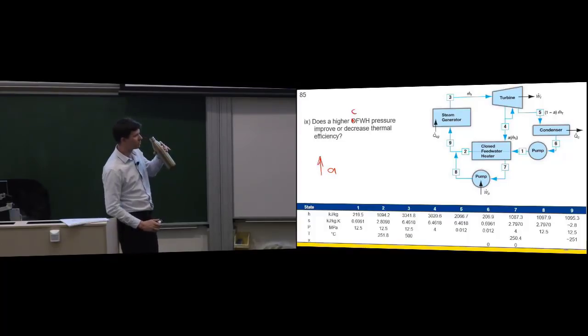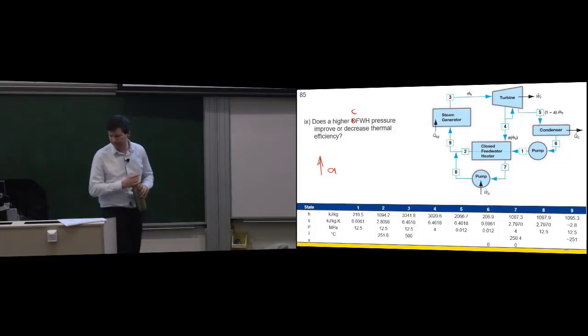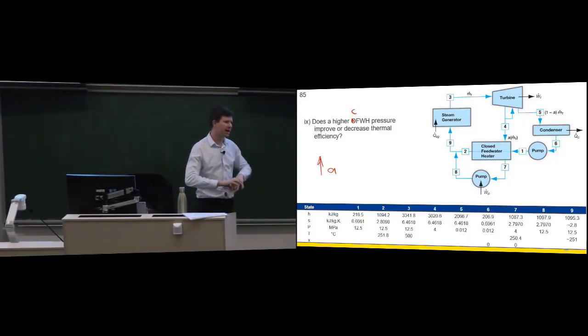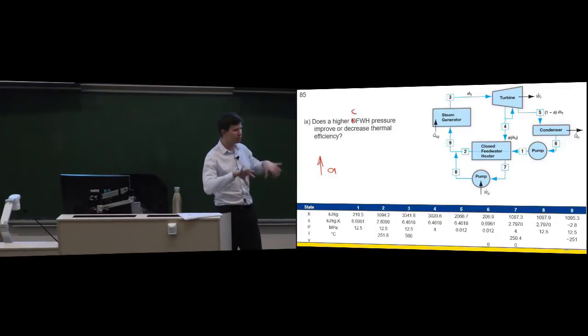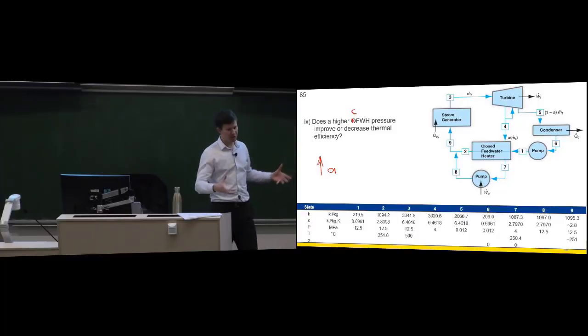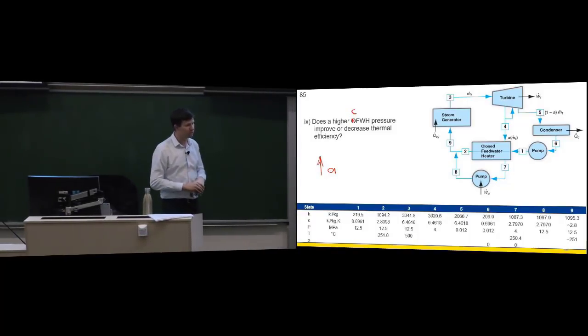Closed would be more expensive. Yeah. An open feed water heater would be a pressure vessel with a few nozzles. A closed feed water heater would be a pressure vessel with a header at both ends and tubes running through it, potentially if it's a shell and tube.